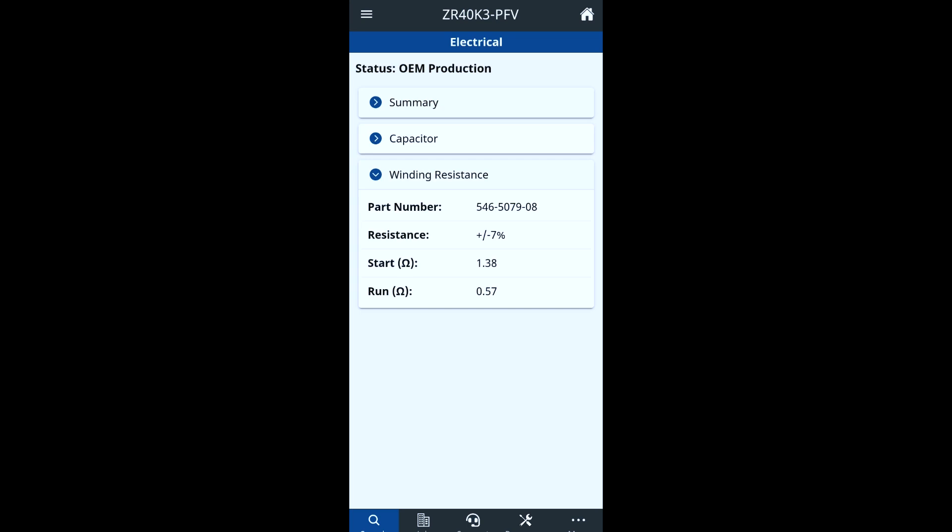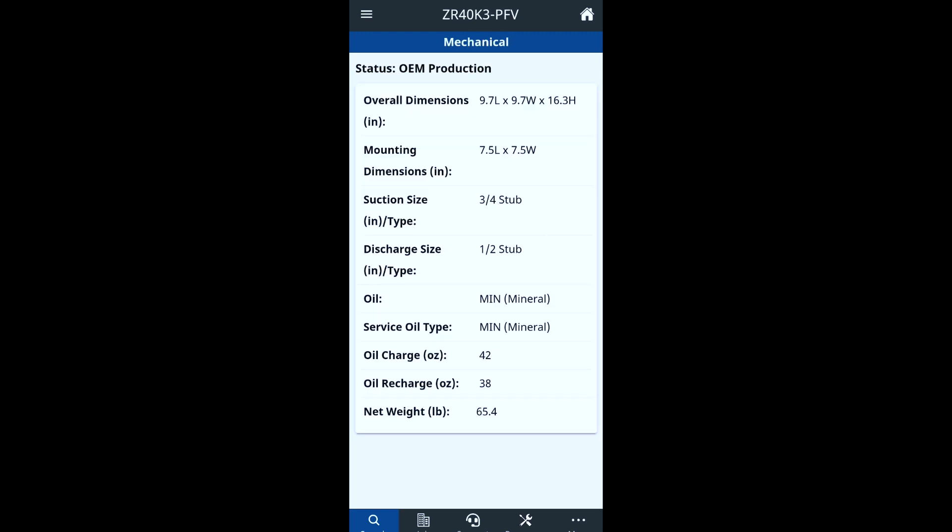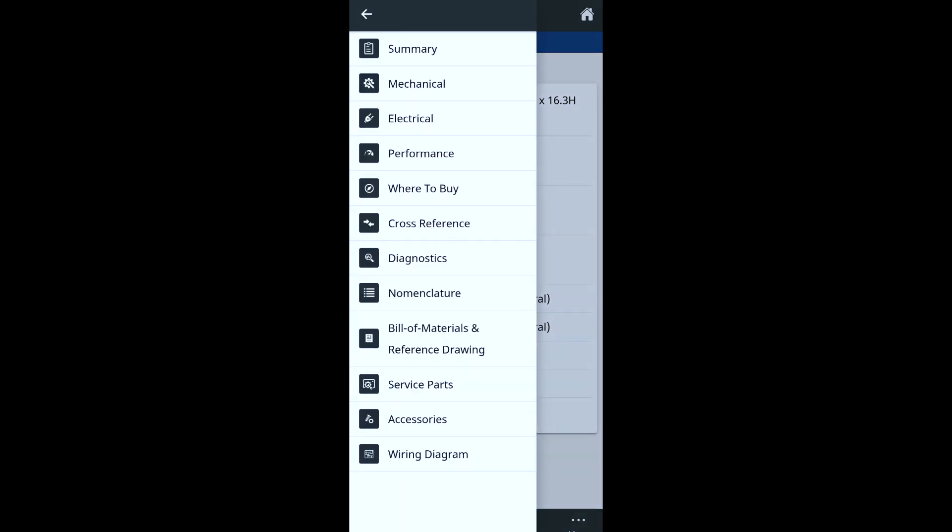Another thing — I wish they had the specs for the insulation test for the scroll-type compressor, but they do have your winding resistance. I'm guessing this is from common to each terminal, so start winding to common should be 1.38 ohms and run to common will be 0.57 ohms. This will show you your general voltage, locked rotor amps, and mechanical data will give you all your specifications — suction line size, discharge line size, mineral oil — all the general things.